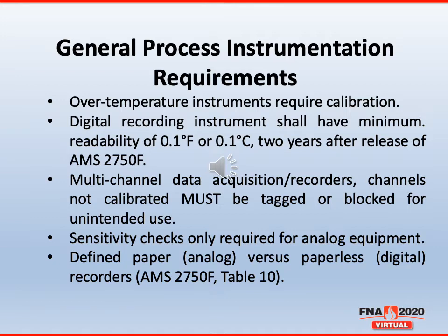Likewise, with multi-channel data acquisition systems or recorders, channels that are not calibrated now must be tagged or blocked for unintended use. So somehow you're going to have to block those channels that aren't being used. For instance, you have a vacuum furnace and you're using 3 channels for your load TCs and the other 9 channels are not being used. Those channels in the back of the recorder will need to be blocked off, or some sort of documentation or tag that shows that they are not being used.